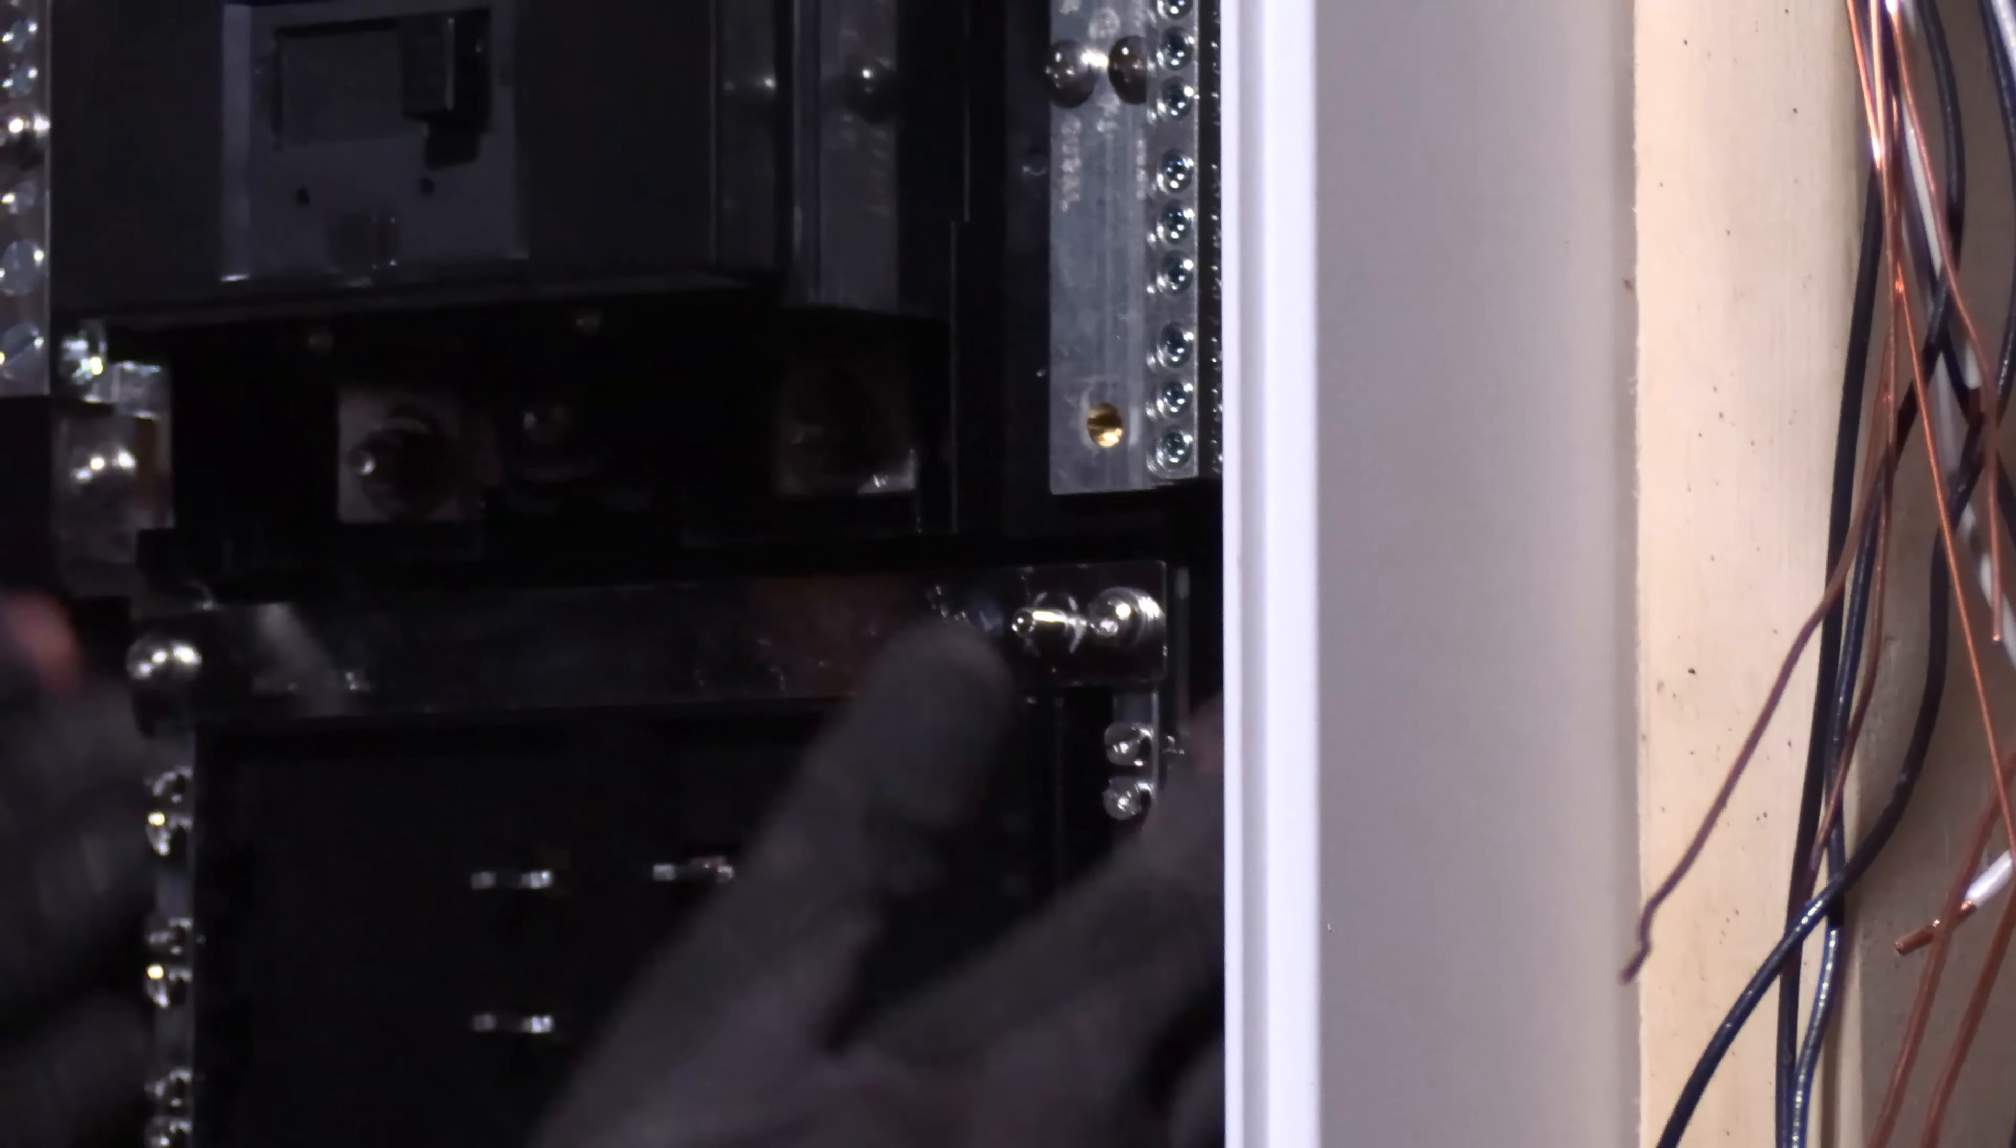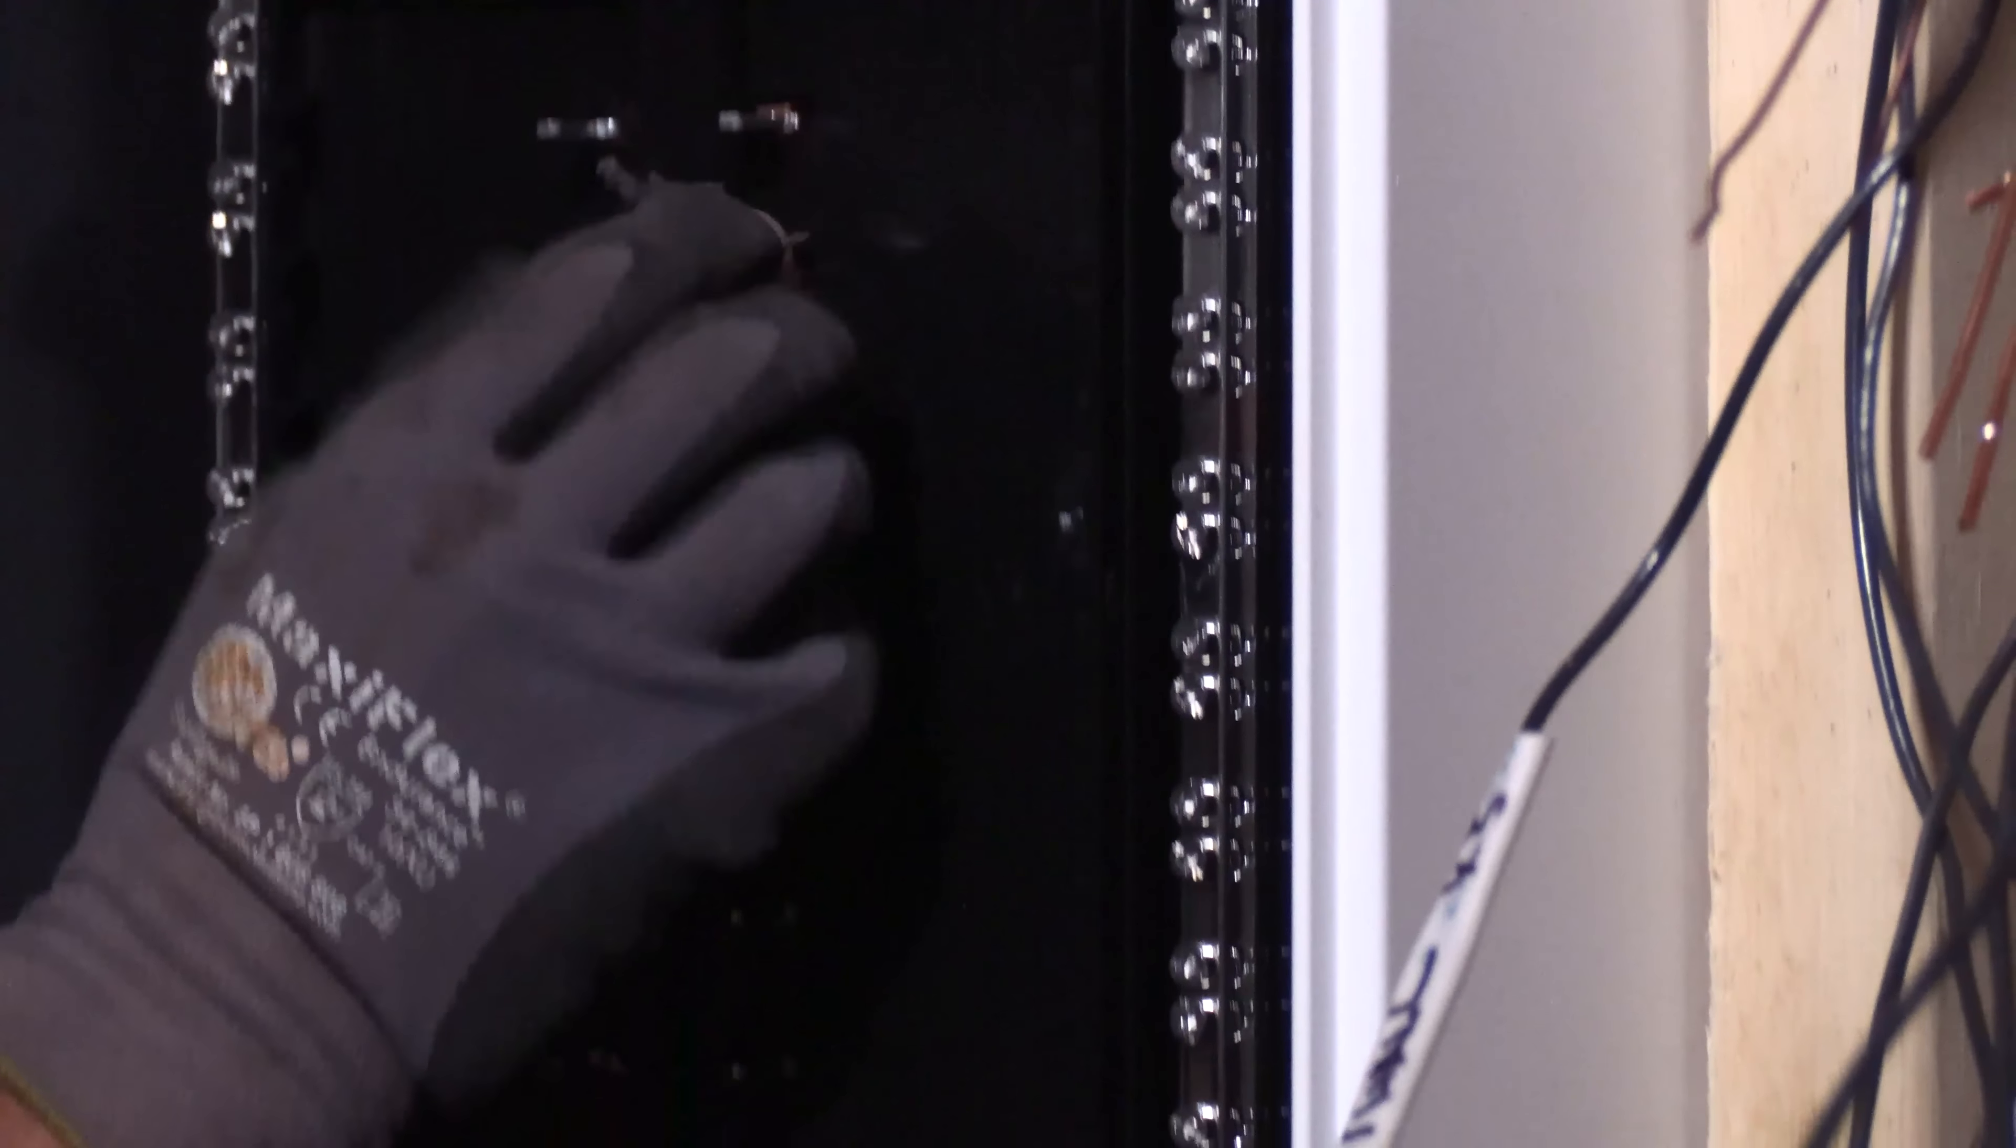Every circuit is individually monitored and controlled. It's really a beautiful piece. This is a sub panel. So neutrals and grounds are separated. I've removed the bonding strap between the ground bar and the neutral terminals.